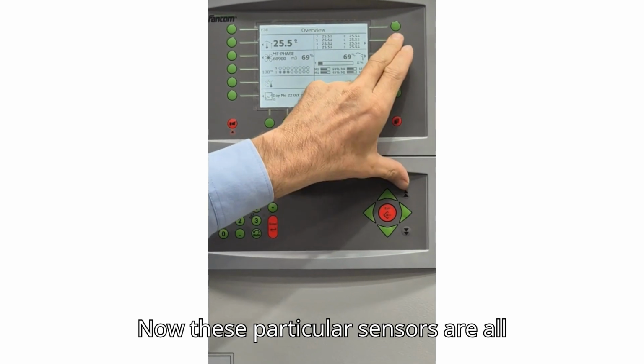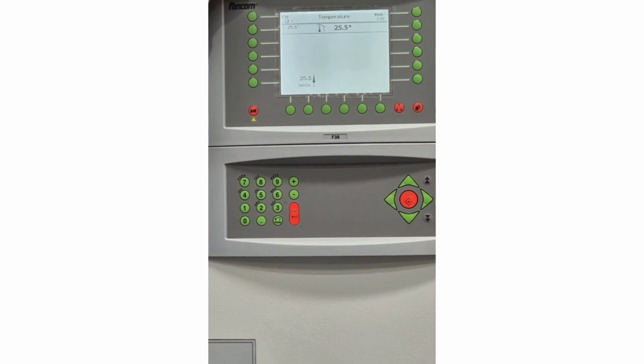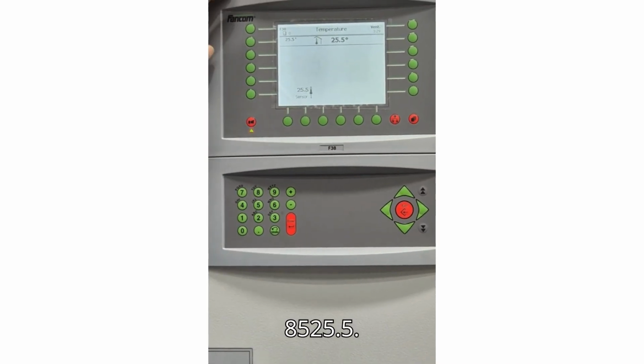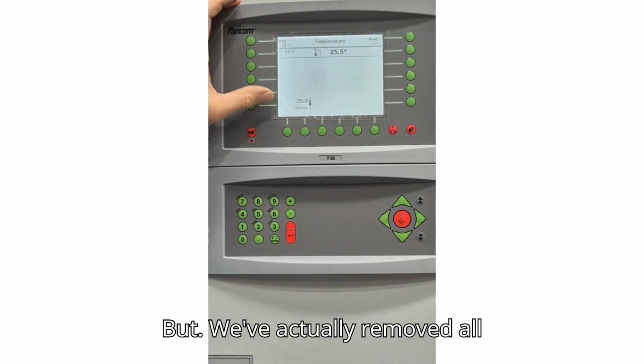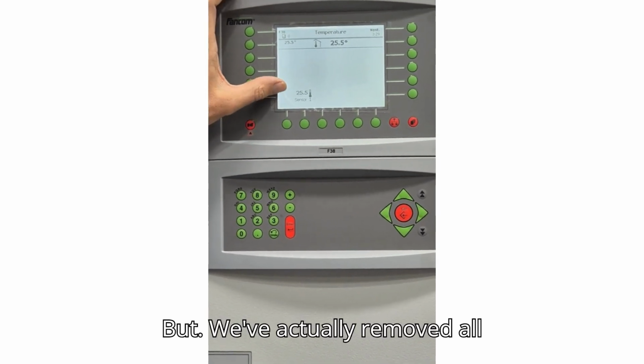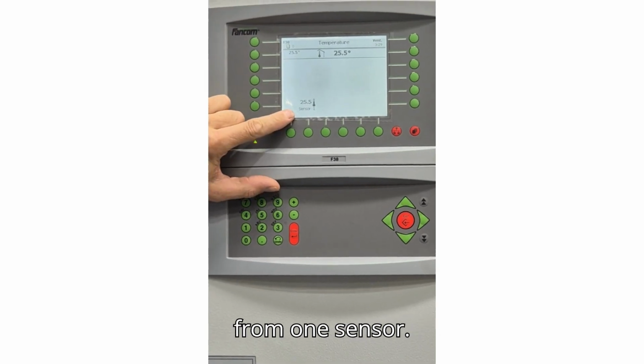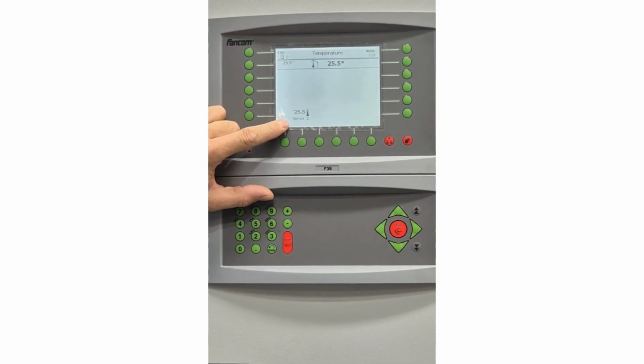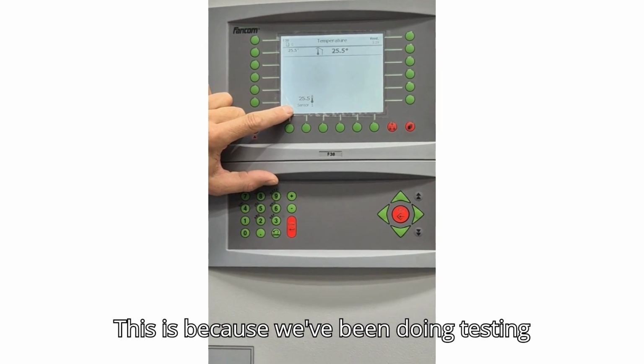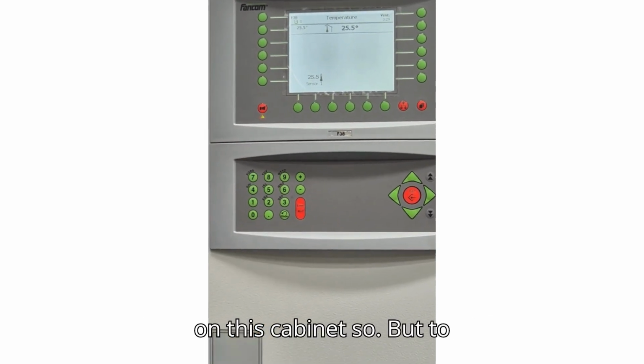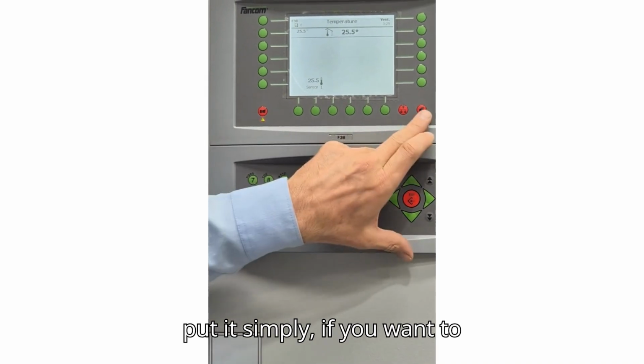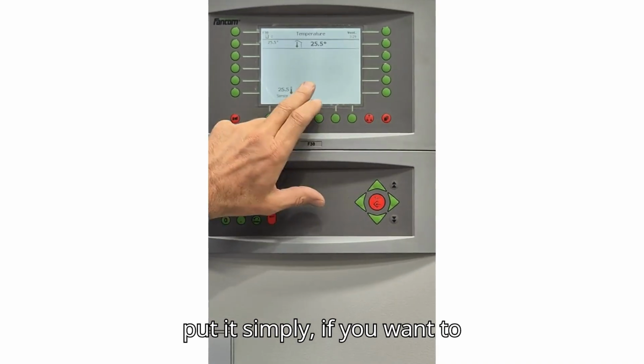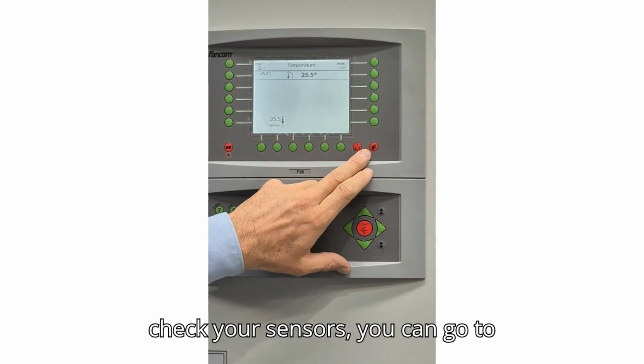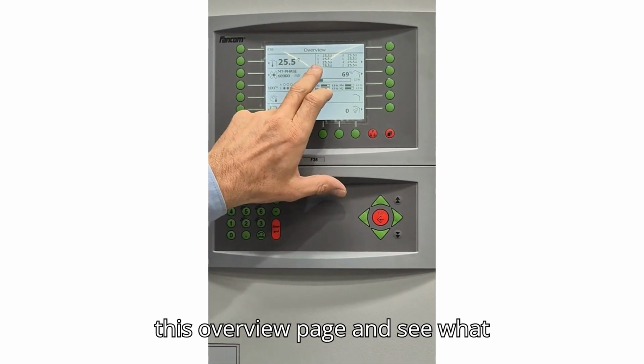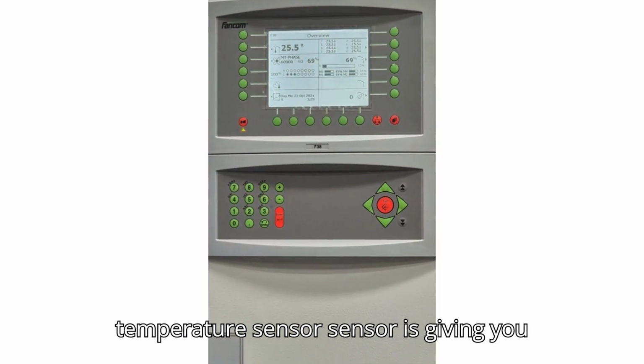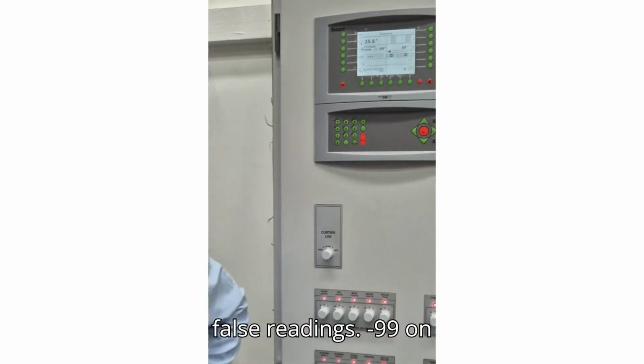Now these particular sensors are all reading 25.5, but we've actually removed all of our sensors and we're only running from one sensor. This is because we've been doing testing on this cabinet, but to put it simply, if you want to check your sensors, you can go to this overview page and see what temperature sensor is giving you false readings.